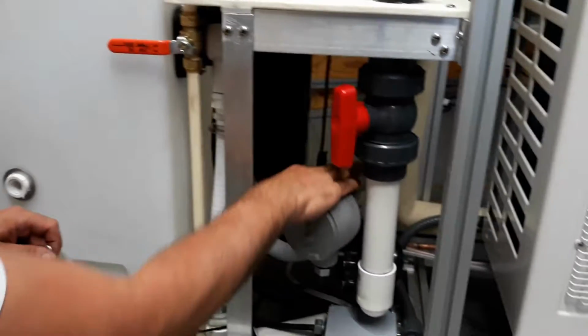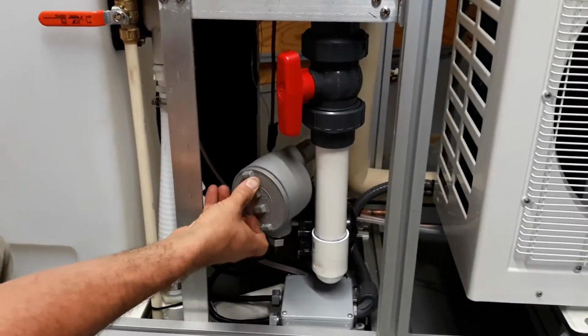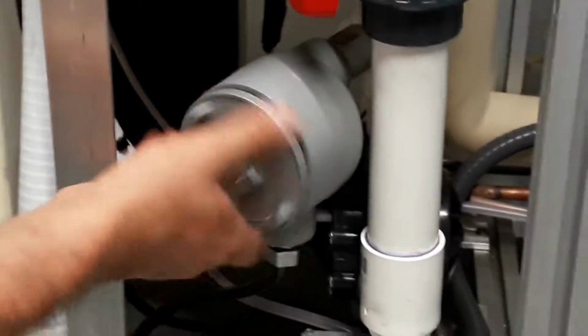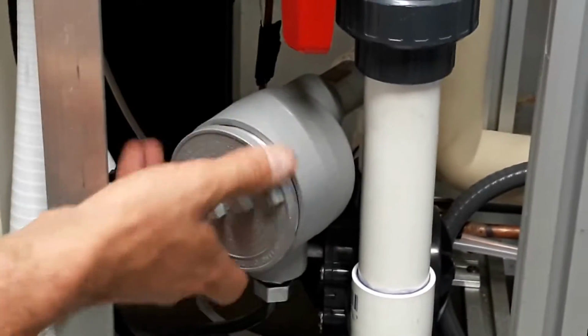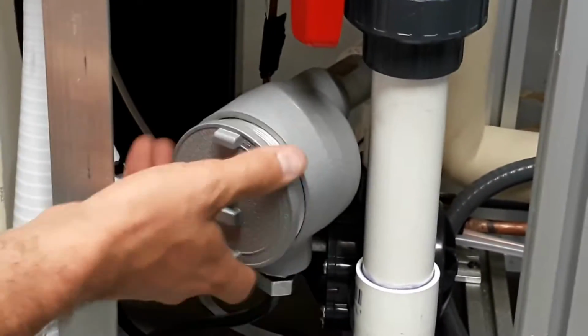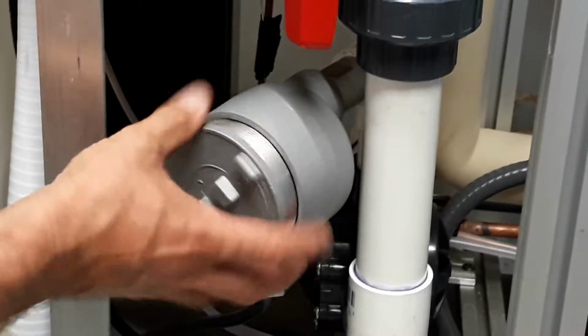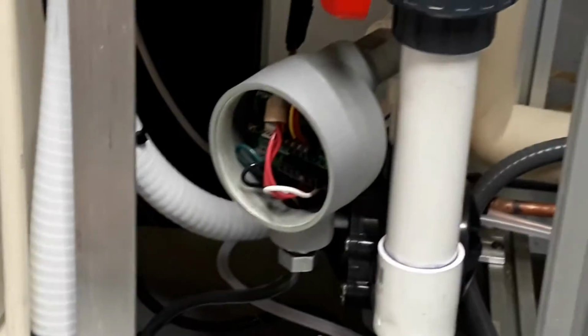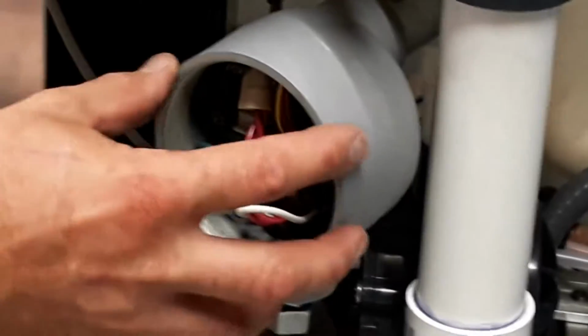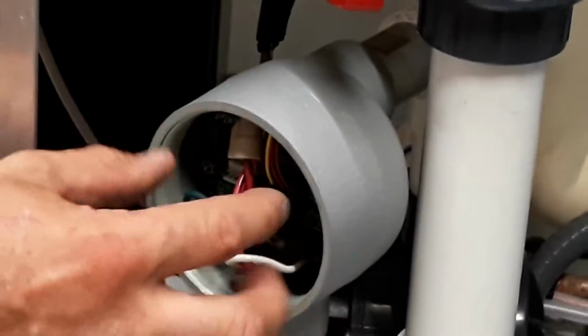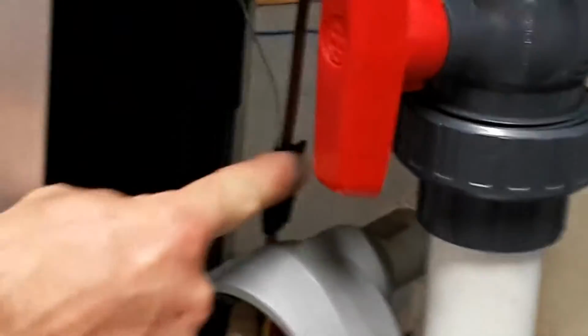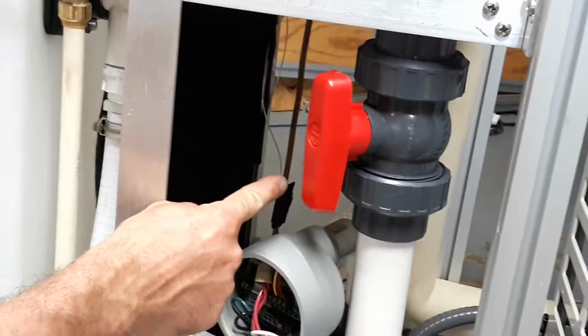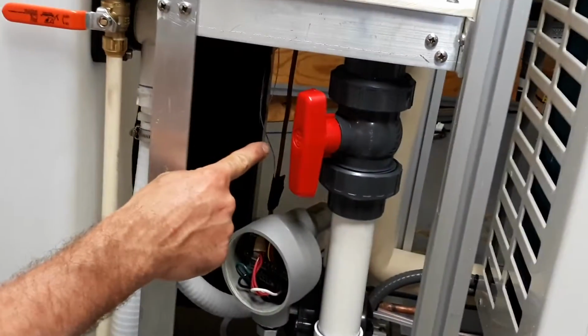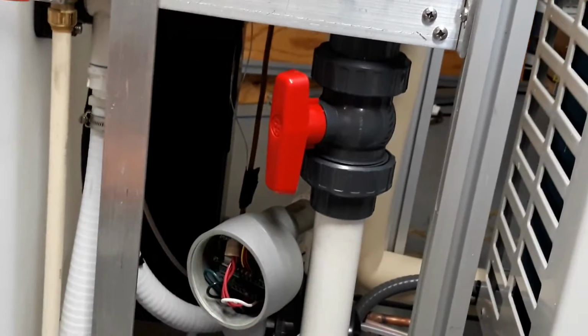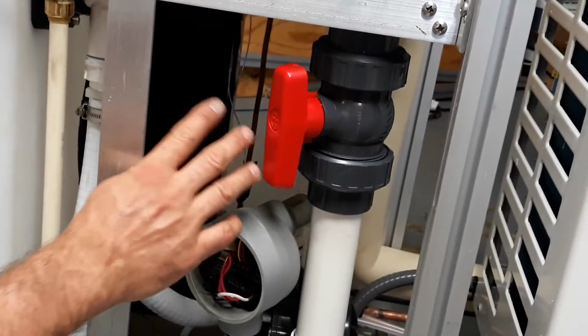This here is a flow control, which is measuring the flow of water to the heat exchanger, which is highly critical, and it's constantly monitoring the amount of flow, and for it to be proper, for not having a freeze-up situation.